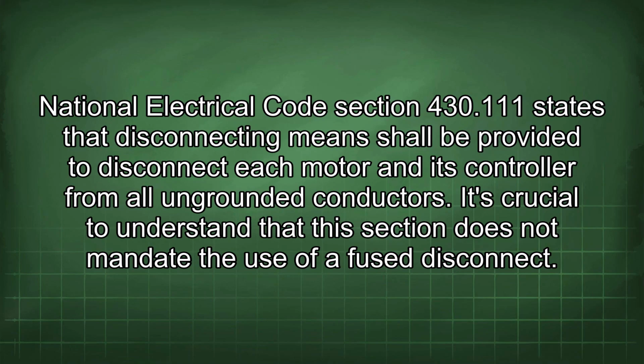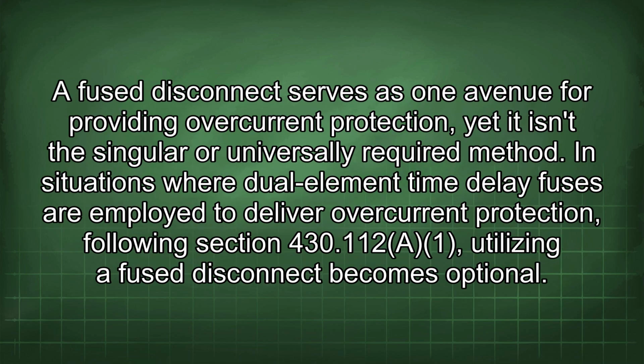National Electrical Code Section 430.111 states that disconnecting means shall be provided to disconnect each motor and its controller from all ungrounded conductors. It's crucial to understand that this section does not mandate the use of a fused disconnect. A fused disconnect serves as one avenue for providing overcurrent protection, yet it isn't the singular or universally required method.